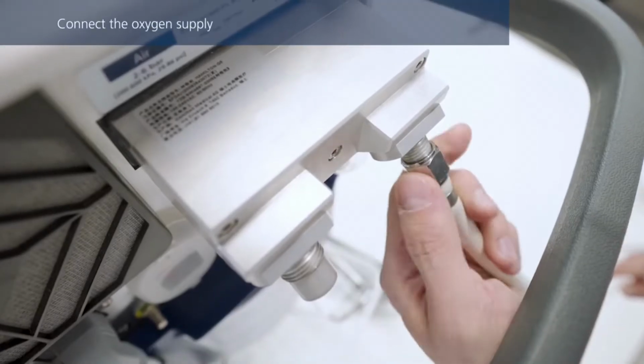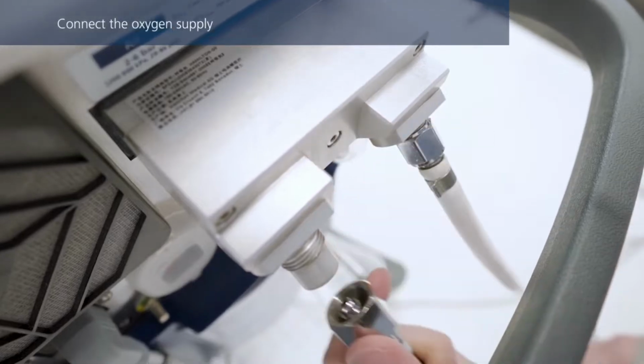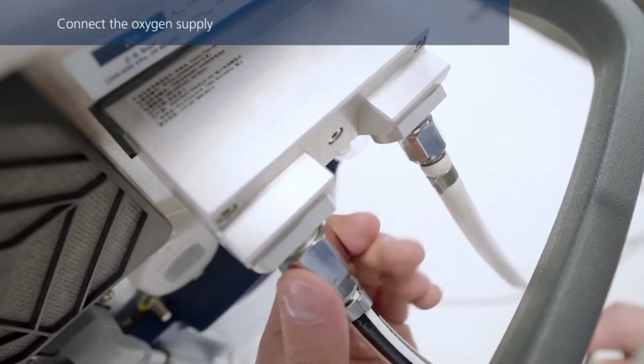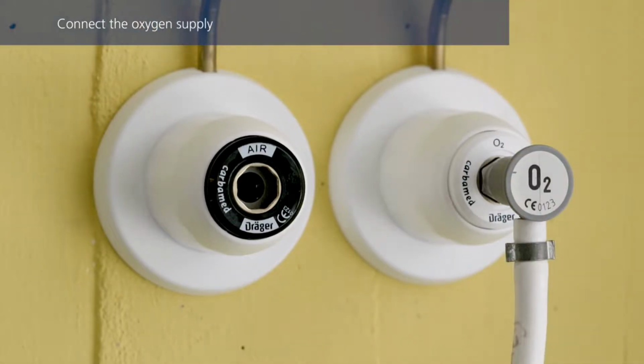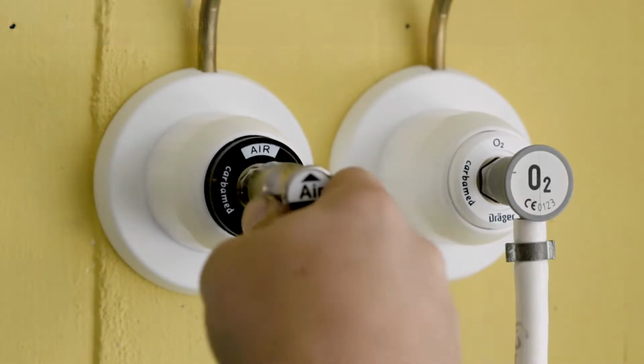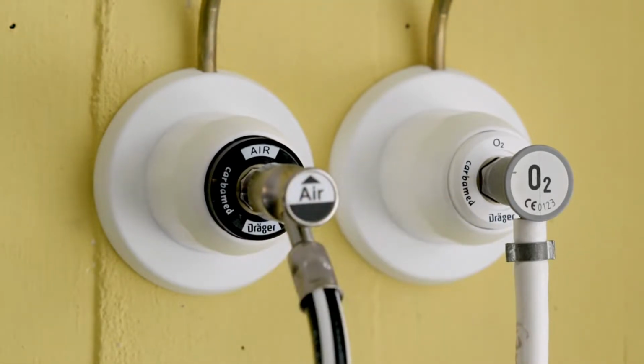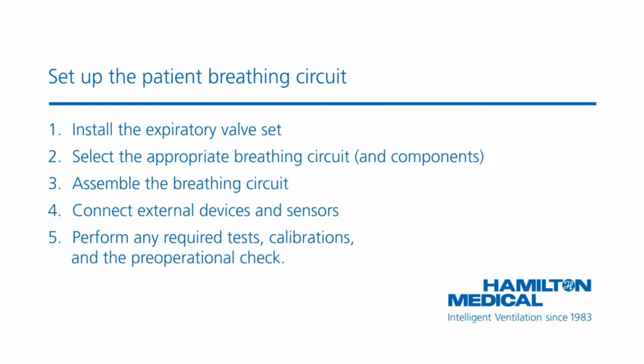If you haven't done so already, connect the oxygen and air gas hoses to the ventilator, and then to the gas supply or gas cylinder. To connect the breathing circuit, do the following. First, install the expiratory valve set. Then, select the appropriate breathing circuit and components. Third, assemble the breathing circuit. Then, connect the external devices and sensors. Finally, perform the pre-operational checks.